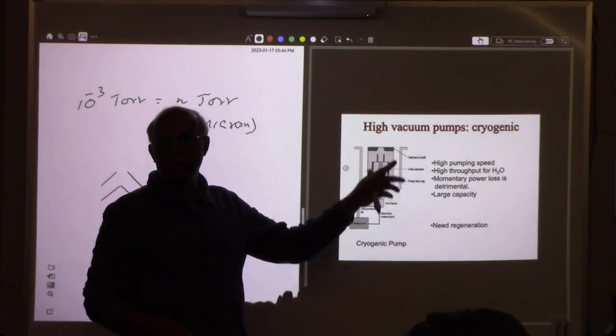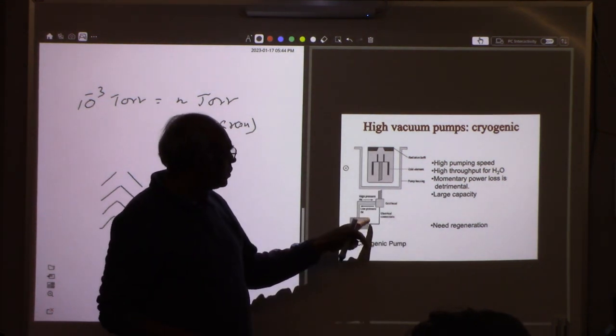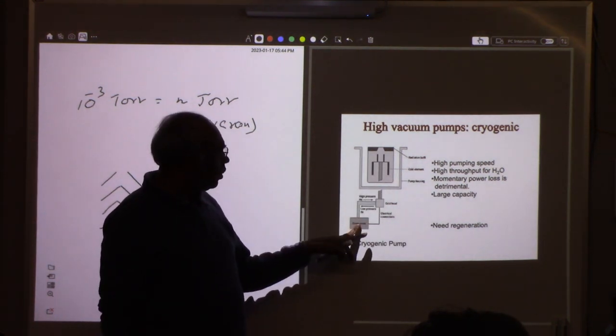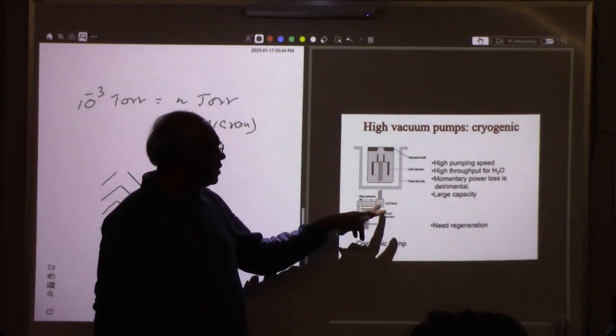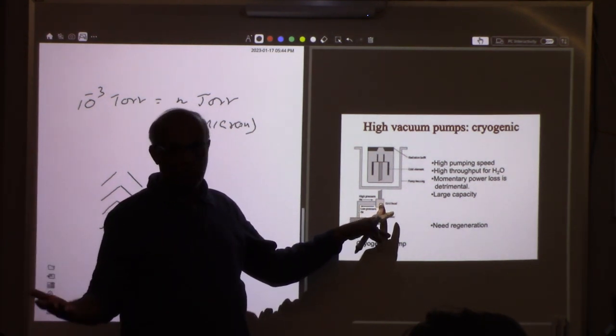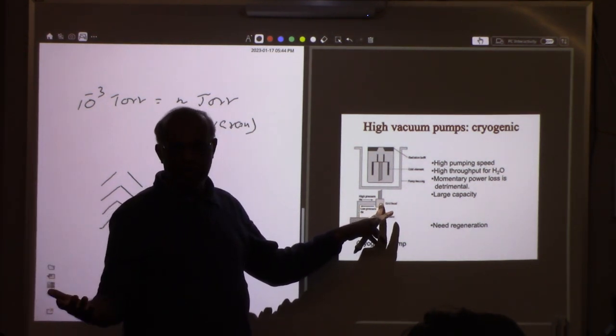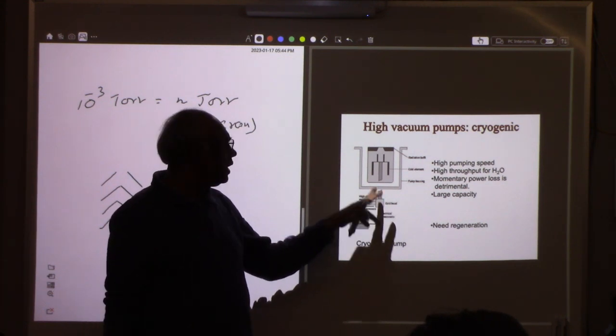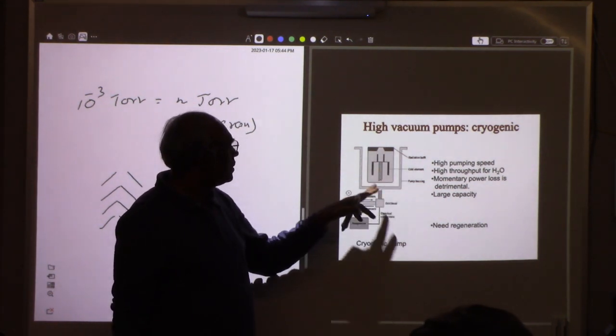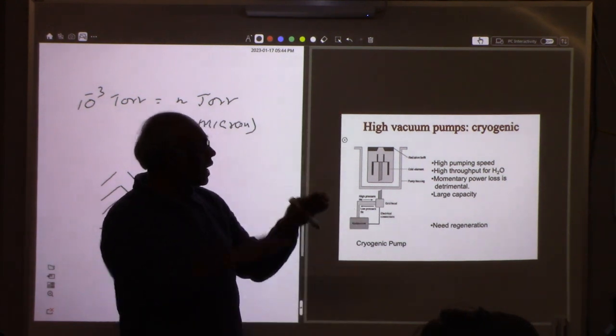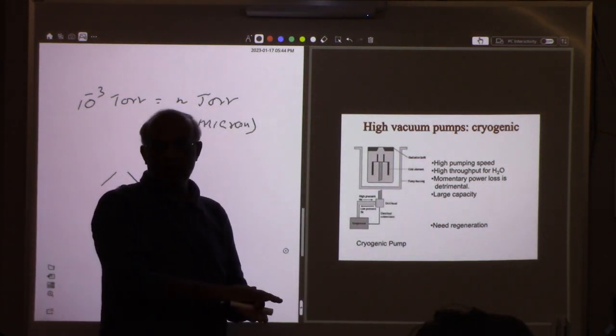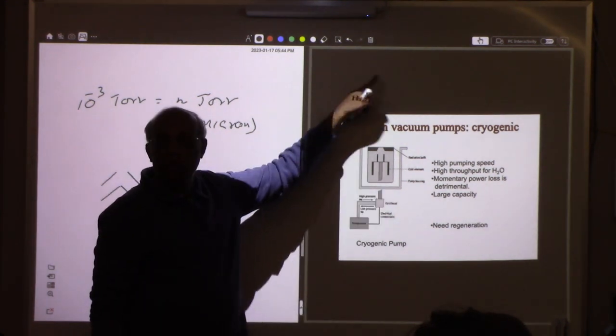That's very efficient. Once you cool this down, you just turn on the compressor, then it gets down to about close to 4 Kelvin, liquid helium. Then this part becomes so cold, so all the gas molecules in your chamber will condense onto that surface, and you get very low vacuum here.